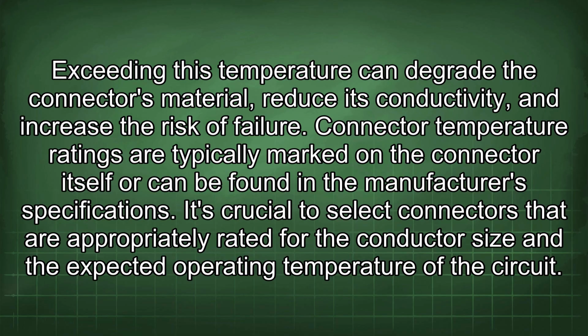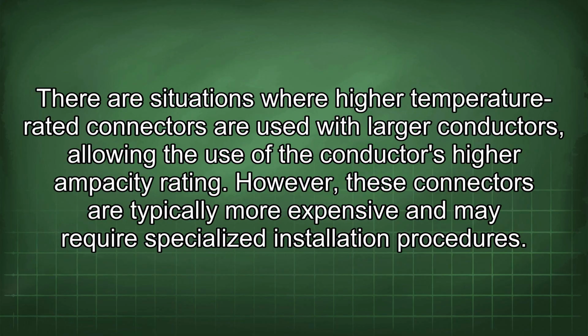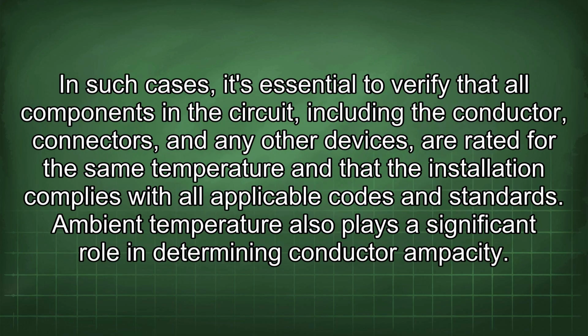Exceeding this temperature can degrade the connector's material, reduce its conductivity, and increase the risk of failure. Connector temperature ratings are typically marked on the connector itself or can be found in the manufacturer's specifications. It's crucial to select connectors that are appropriately rated for the conductor size and the expected operating temperature of the circuit. There are situations where higher temperature rated connectors are used with larger conductors, allowing the use of the conductor's higher ampacity rating. However, these connectors are typically more expensive and may require specialized installation procedures. In such cases, it's essential to verify that all components in the circuit, including the conductor, connectors, and any other devices, are rated for the same temperature and that the installation complies with all applicable codes and standards.